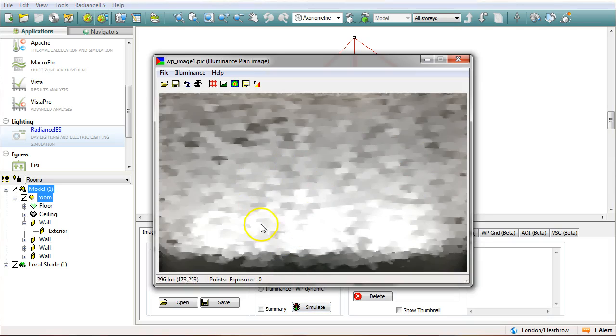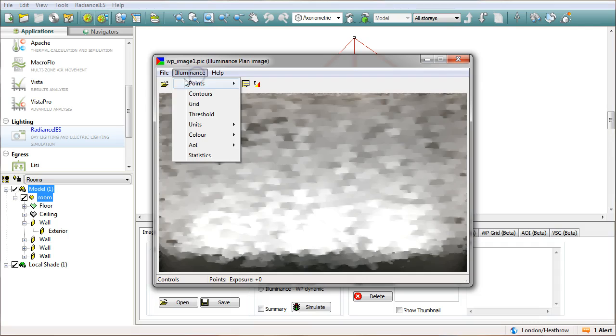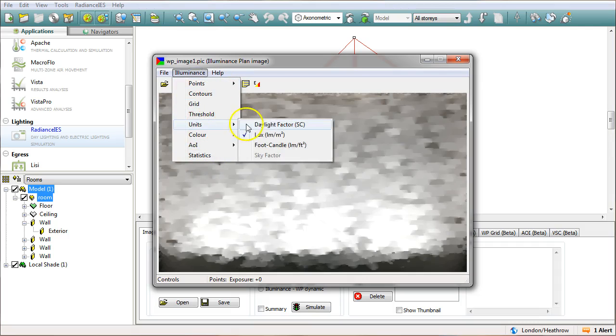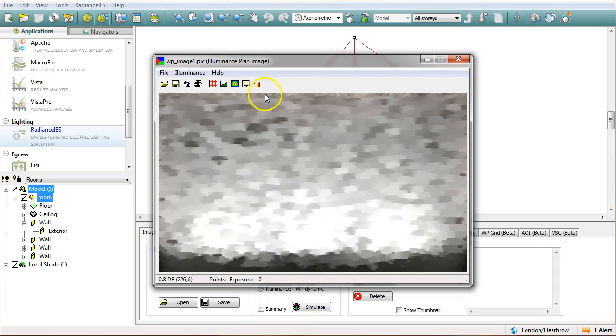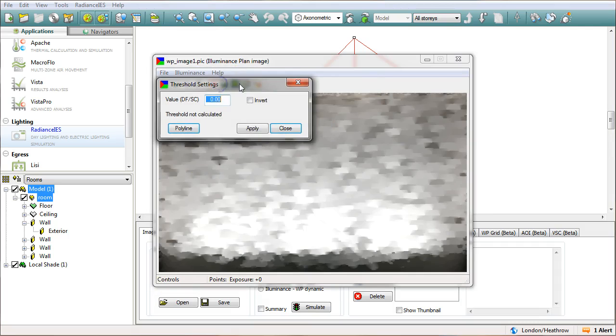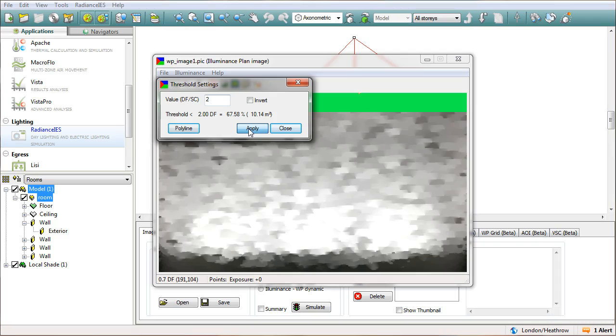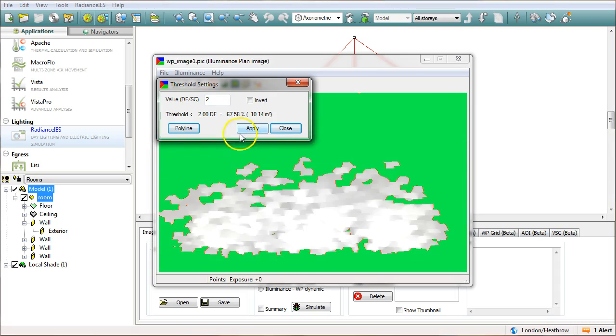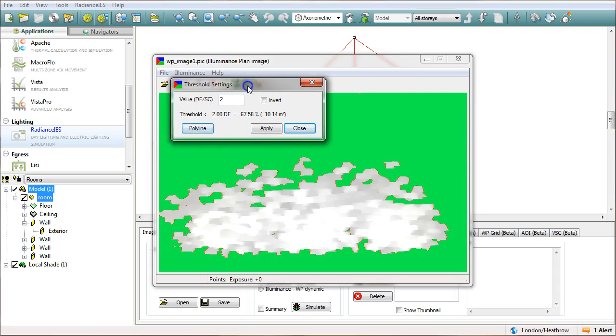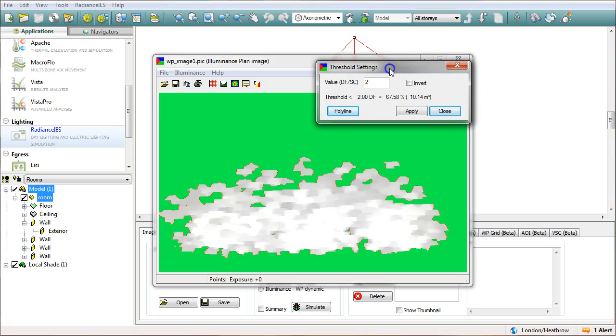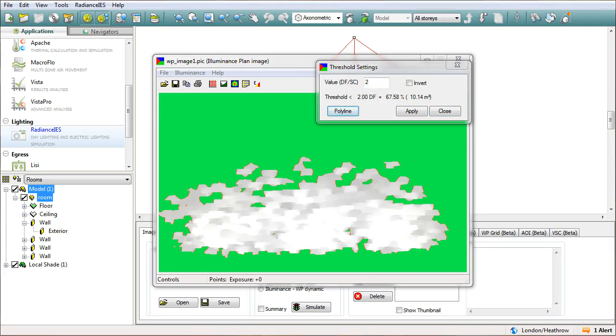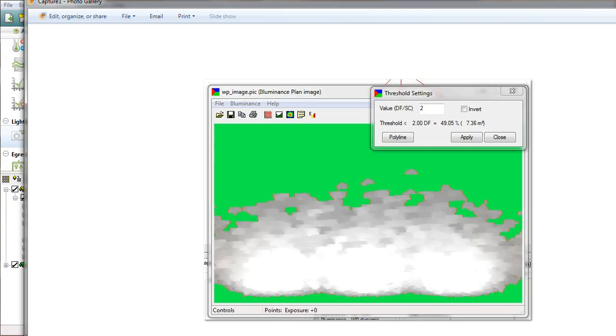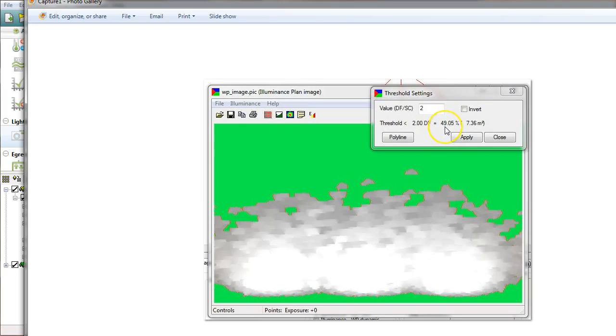Okay so what we have here now is our map and we will look and change our units to daylight factor and we look for a daylight factor of two and apply. Okay so what we're seeing now is that 67 almost 68 percent of the floor area has a daylight factor of less than two.